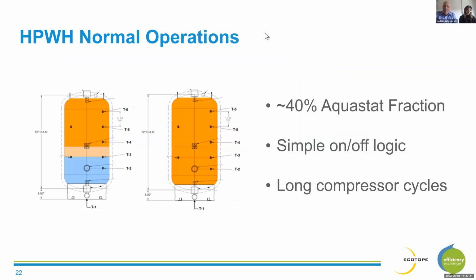So we have a pretty simple and, I would say, somewhat ingenious way to manipulate the controls for these heat pumps to allow for load shifting. Under normal operations, there's an aquastat about 40% of the way up the primary storage tank, and the cold water floods into the bottom of the tank, and when it gets up to about 40% of the way up the tank, that aquastat sees that there's cold water and says, okay, better recover, and it sends a signal to the heat pump to turn on.